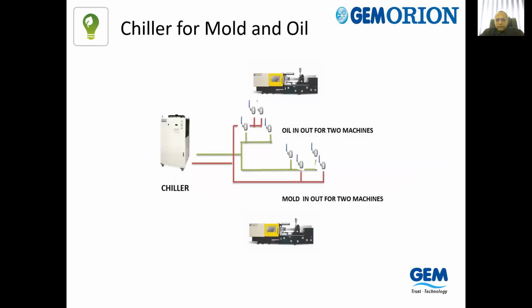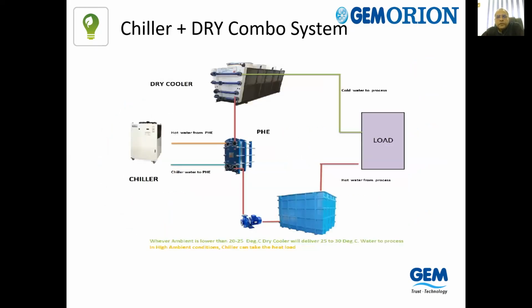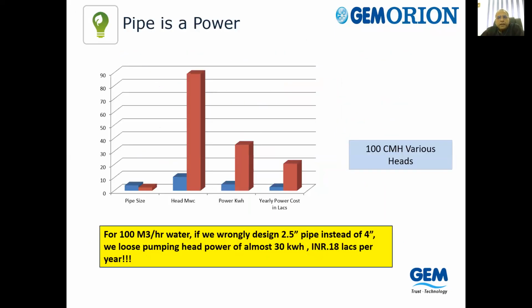So a typical chiller for multiple machines, you have a common line, and we have two separate lines, one for the oil line and one for the mold. So this is how we distribute for multiple machines. Suppose you want to combine a dry cooler with a chiller, this could be a typical system where we can adopt this process, so that we have a heat exchanger in between and a dry cooler can be used along with the chiller. At lower ambient, you can maintain with the dry cooler; at higher ambient, you go in for a chiller.